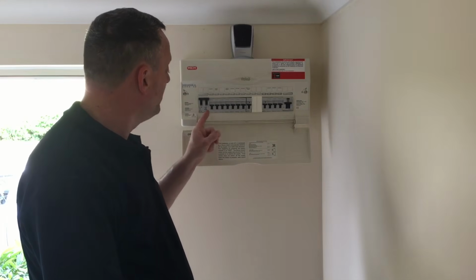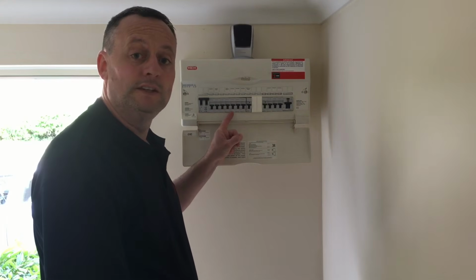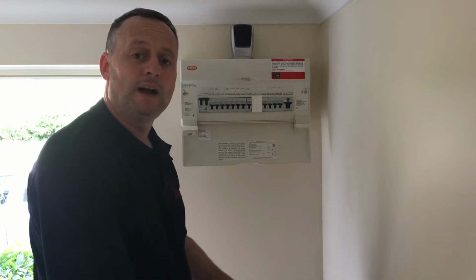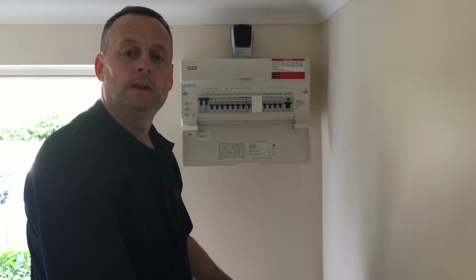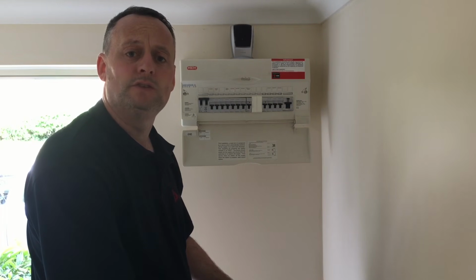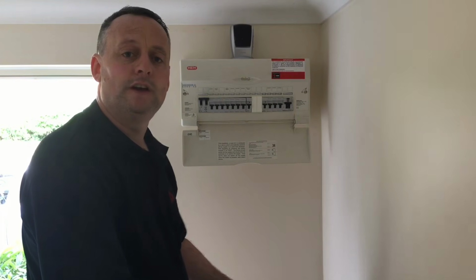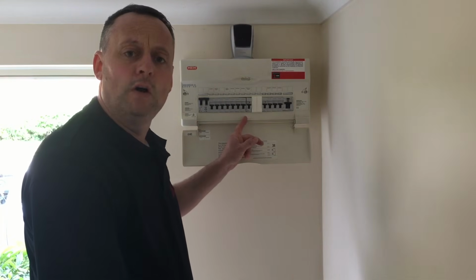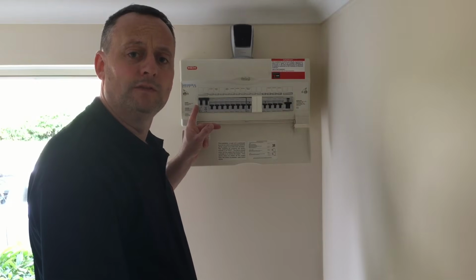I'm going to need to isolate that, turning off both line and neutral. Before doing so, it would be advisable to turn off individual, in this case circuit breakers, to reduce the amount of load that I would be switching off. It is advisable to tell the customer before turning off the electricity, not just for inconvenience sake, but if they have sensitive electronic equipment that's in use, it would not be advisable just to turn the power off to those types of equipment. So it's best they power down those items before you turn off the electricity within the distribution board itself. I'll turn off each circuit breaker in turn before I turn off the main switch itself.